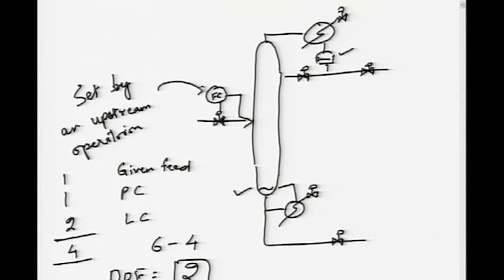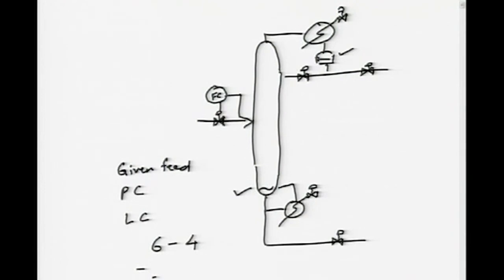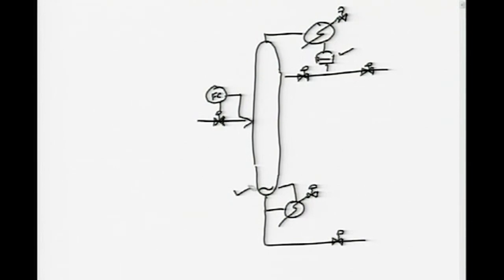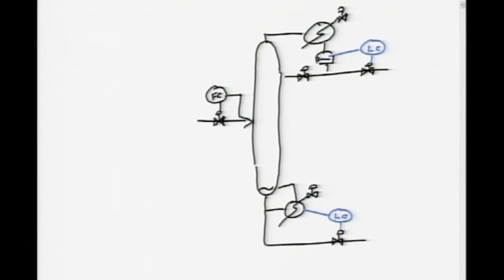Given this degrees of freedom of two, the operator is free to set two things to get the separation that he wants. Depending on how the level controllers are set, the level controller may go this way. The pressure controller typically always uses cooling rate. That leaves the operator to set the reflux, called L, and the reboiler duty, called Q. This is the LQ structure.